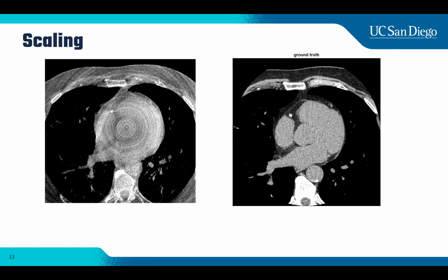But I'm with you on this. It's a mystery why we still have these large, thick ring artifacts, or circular artifacts. And I guess one question is, when you did your transformation from your readouts, your raw data, did you take into account that the detector itself had a certain curvature?